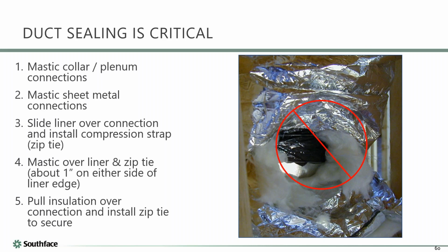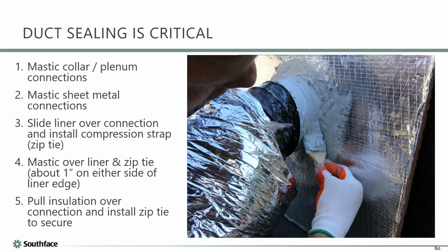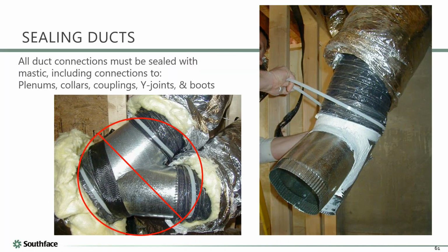Putting sealant on is pretty important. It's all about where the pressure barrier is and making sure it's done continuously. With flex duct, you can do it from the outside, like you're seeing in this picture here, but a lot of times when you're assembling it, it's probably better to put it on the fitting and then slide the flex over it, then put the zip tie on and fasten it. I thought maybe you were going to say something, so jump in if you want to.